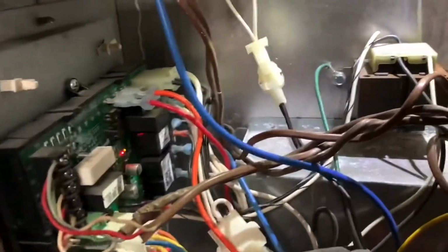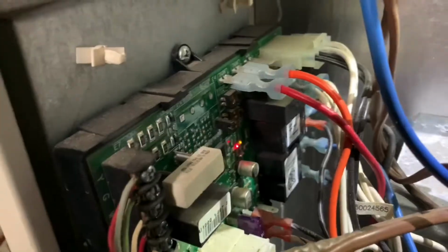If I cut this wire right now, we will have a loss of flame. The amber light will go out. The amber light on the board will go out. And that's what I mean on that. So you see the amber light that says flame? The amber light that says flame will go out if I cut this wire.